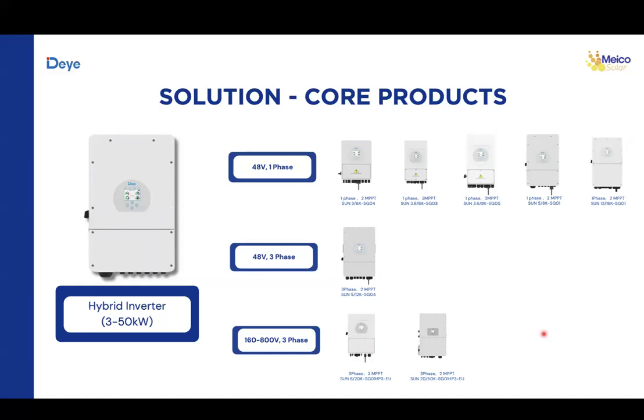Really important here is the 16 pieces that you can put in parallel, 16 inverters, which in this case is for only single phase split phase solutions. When you do that with a 12K inverter, then you will have a really big project that you can fit with Deye solutions. So it's not only for residential solutions, but you can as well get really good solutions for commercial and small industrial, okay? The smallest hybrid inverter, three-phase, Henrik, that we have, that question from Henrik, it's 12 kilowatt, okay? The smallest inverter for three-phase low voltage, 12 kilowatt, okay?